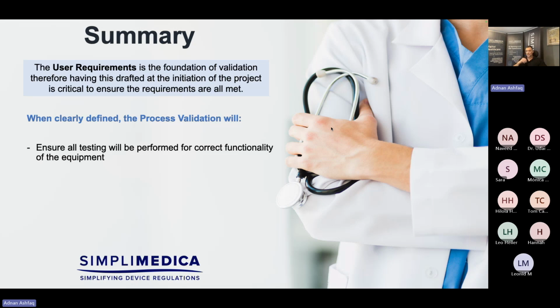So the question is, do we then retrospectively create a user requirement? Well, there may be little benefit in creating a user requirement specification. I would say it's more beneficial developing a design requirements document, which would then be the basis of the validation on the following requirements. So, for example, let's take an example of environment. What type of environment does it need to be in? Does it need to be in a clean room, or is it okay to be in a dirty environment which is uncontrolled? That's a requirement. So it's useful to put that in a design document, which could be a design requirements document as opposed to user requirements.